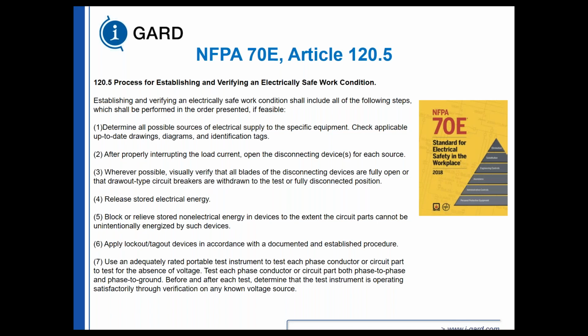If we look at NFPA 70E, and this deliberately is the 2018 version of 70E, establishing and verifying an electrically safe work condition: obviously, we have to determine all possible sources of our electrical supply to the specific equipment, and ensure that all our drawings are up to date, so our electricians know what they have to shut off in order to establish a de-energized workplace. But just because you shut everything off doesn't mean you have a safe condition yet.